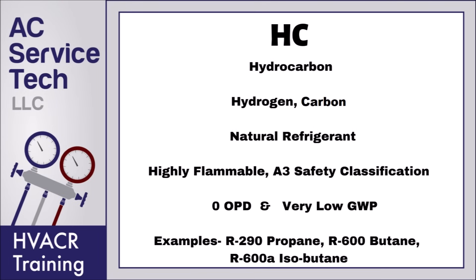HC refrigerant is hydrocarbon, made up of hydrogen and carbon. It is a natural refrigerant though highly flammable. It's in the A3 safety classification but has zero ODP and very low GWP. An example is R290, which is propane. R290 can be used in applications that already use R22, however it cannot be used as a retrofit for R22 due to its high flammability, but it can be used in commercial and industrial applications where proper safety controls are in place. R600a continues to be used more and more in domestic refrigeration systems that need a very low refrigerant charge.